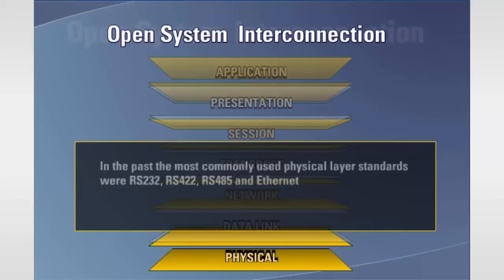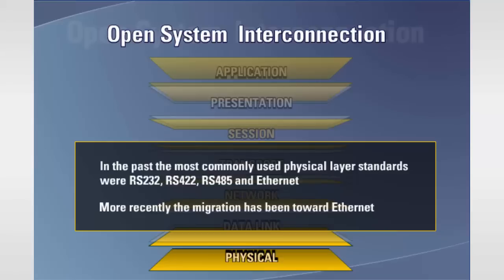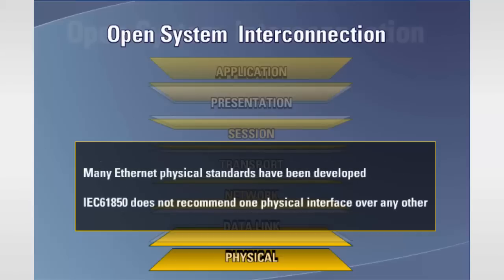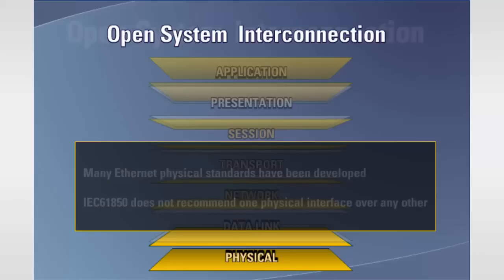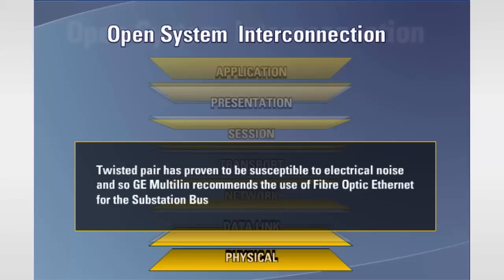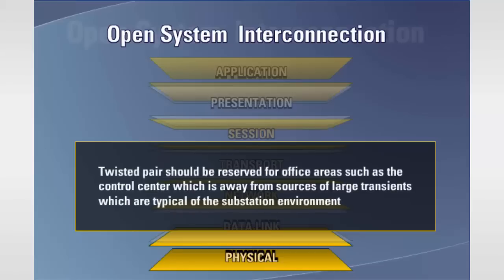In the past, the most commonly used physical layer standards by utility and industrial power system applications were RS-232, RS-422, RS-485, and Ethernet. More recently, the migration has been toward Ethernet. Over the years, many Ethernet physical standards have been developed. IEC 61850 does not recommend one physical interface over any other. However, twisted pair has proven to be susceptible to electrical noise, and so GE Multilin recommends the use of fiber-optic Ethernet for the substation bus. Twisted pair should be reserved for office areas, such as the control center, which is away from sources of large transients, which are typical of the substation environment.